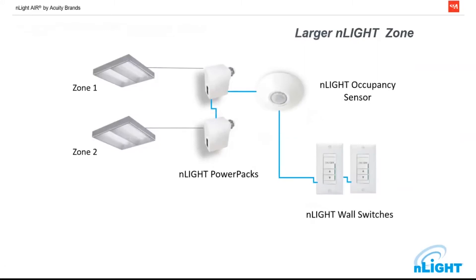Now we've added a second switch, a second zone or power pack, and an occupancy sensor. Again, we are Cat5-ing between our power packs, our occupancy sensor, and our switches, and we are running regular power out from our power pack to our light fixture. Essentially, what we've done is distributed our controls — we've taken what used to be a relay panel in a closet and moved it out into the space for easier wiring and easier configuration.